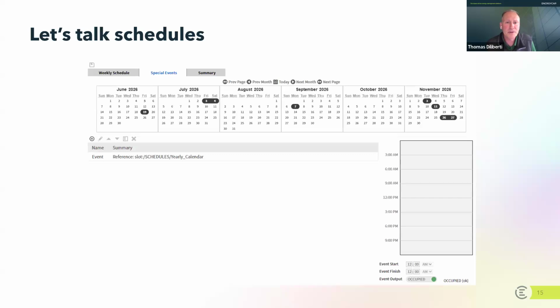The way most building automation systems work is you set up these special events. You can turn things off, set them in an unoccupied mode, or run them differently because it makes sense to do so. And the way most systems work is special event schedules will override weekly schedules. So you don't have to change your weekly schedule. These special event schedules will then dictate how the building will run during those unique periods of time.